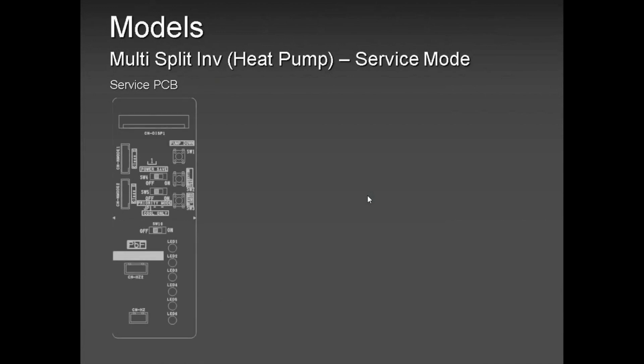So remember, most of the time, I have yet to see an inverter compressor, especially a Panasonic inverter compressor, shot to ground. All I've seen is a seized compressor. And we have found out in most cases, it's either the unit has been oversized, or refrigerant was not added when the pipe length crossed 25 feet.